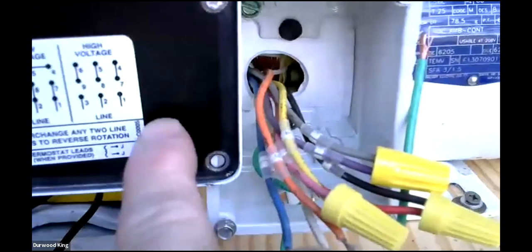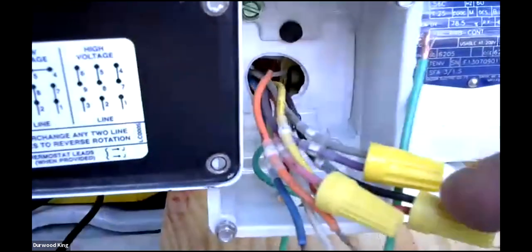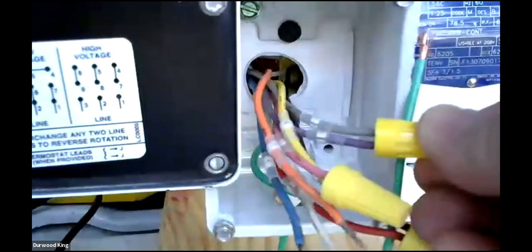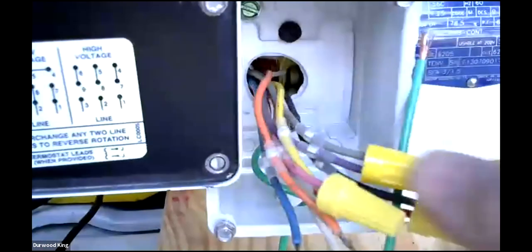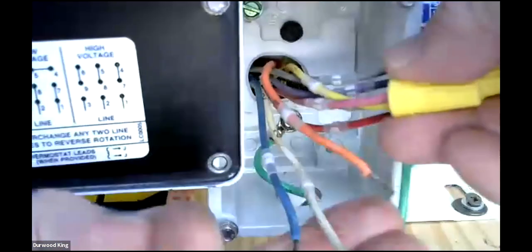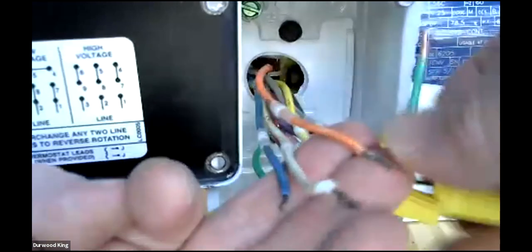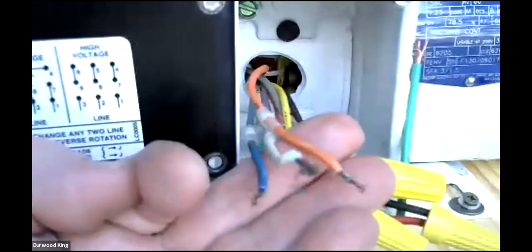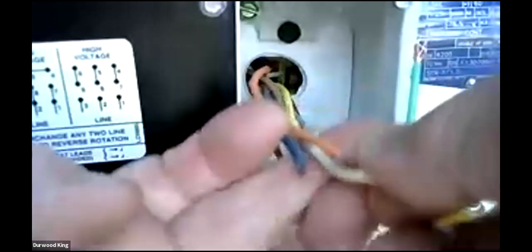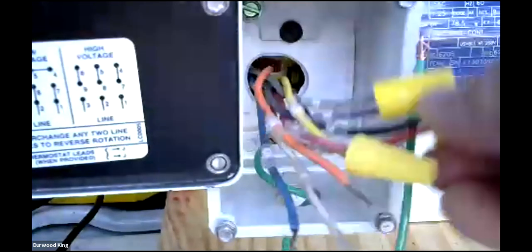So one thing to take note of here is that if you're dealing with a 9-wire motor, it's got wires 1 through 9, in your high voltage, every wire nut has 2 wires. Everything's in pairs. Everything's in 2s. Even your incoming wires, when you tie these to the starter, you've got your wires coming into this from the starter, and that's going to give you two wires per wire nut. You have a 1 and a 2 and a 3 coming in, so everything in that cat head is going to be in pairs if it's wired high voltage. Does that make sense?